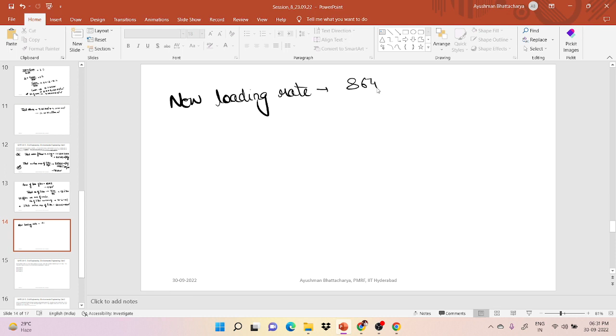Therefore, the new loading rate will be: how much water needs to be filtered in a day, 86400 meter cube per day, divided by the total surface area of the filter we just calculated, that is 600 meter square. So the value comes out to be 144 meter cube per day per meter square. Just be careful about the units. It is in meter cube per day per meter square, since they have asked us about the loading rate. So the new loading rate is 144 meter cube per day per meter square. This is the answer.